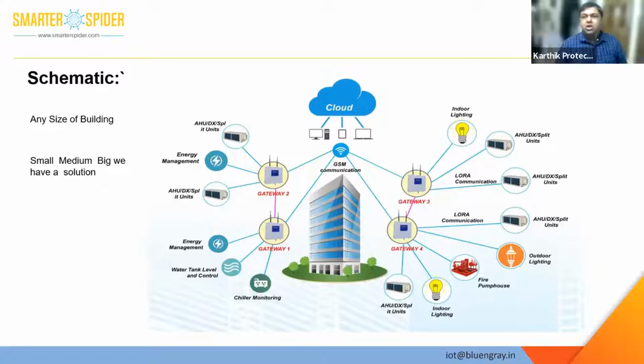So we monitor all these. We do a survey of the entire building, and once we have a list of utilities that are required to be monitored and controlled, we divide the entire building into multiple segments. Each utility has its own wireless module, and they are mapped to a gateway. The gateway is nothing but a communication bridge between the wireless modules and the cloud.